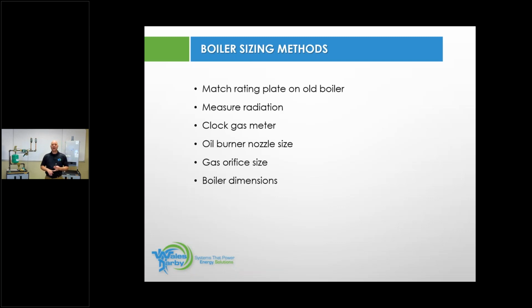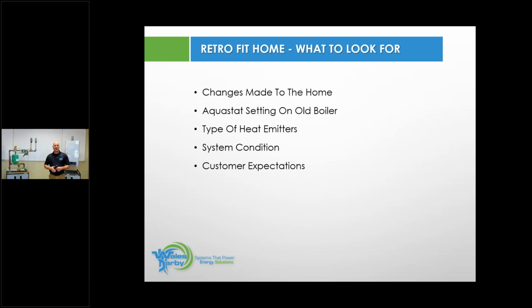You could take the nozzle out of the oil burner and look at the nozzle size, and if it's a 1 gallon nozzle and it's a 100 psi pump, you burn 1 gallon per hour, and all that tells you really is how much oil it burns in an hour. It doesn't tell you if it's the right size for the home. You could look at the gas orifices, same thing. You know, there's books out there. If you give boiler dimensions, it could tell you the BTU. That really doesn't get it done.